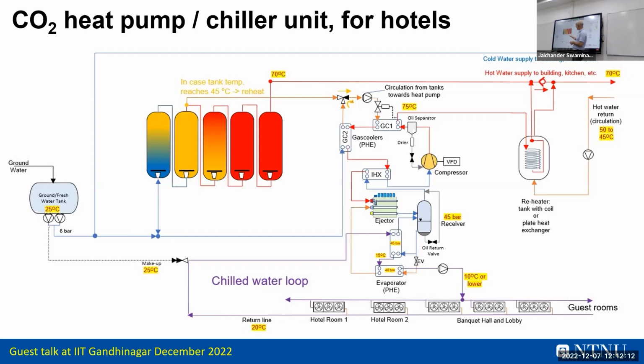Sometimes we may have a challenge here because this water goes back and forth. And if it's charging, the cold water goes in, pushes the hot water out when it's used, and then we charge again. So it's never 100% stratification. So for recovering this, we found out that if you divide the gas cooler into 2 pieces, you also do your water heating in 2 stages.